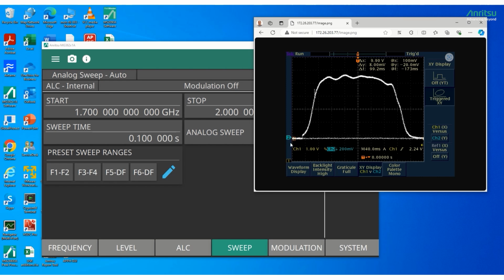As I was mentioning, the ramp signal, the horizontal output signal, is driving the x-axis in the XY mode, which is channel 1. It is set to 1 volt per division here. And as I had mentioned before, the horizontal output is plus 10 volts at the peak. So with channel 1 at 1 volt per division, you can see there are 10 divisions here, from the bottom of the ramp to the peak of the ramp, driving the horizontal axis uniformly. And on the vertical axis, for the Y signal, we were using channel 2, the RF output from the detector.